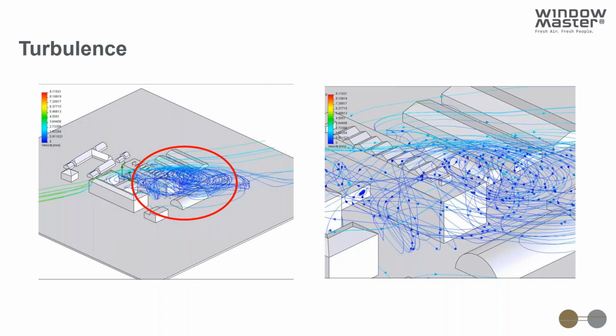Yeah, and here we have just a quick example of some turbulence we can experience at some parts of the buildings, and then determining the wind direction will be very hard if you are locating the weather station in this type of wind turbulence. So it's very important to consider.